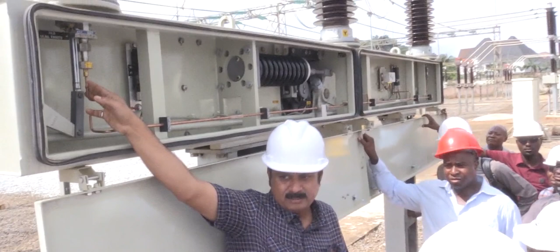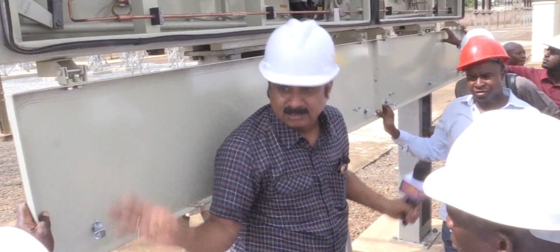Even small dust particles, if they settle on the O-ring surface, can cause a leak. But leakage doesn't mean it starts leaking tomorrow and the entire gas leaks out. The leakage could be very minor, since small dust particles will only give small leakage, and we may get an alarm after 1.5 or 2 years. Still, this can be avoided by cleaning the joint thoroughly with the cleaning agent, cleaning the O-ring, applying new grease, then fitting the O-ring and fixing it.